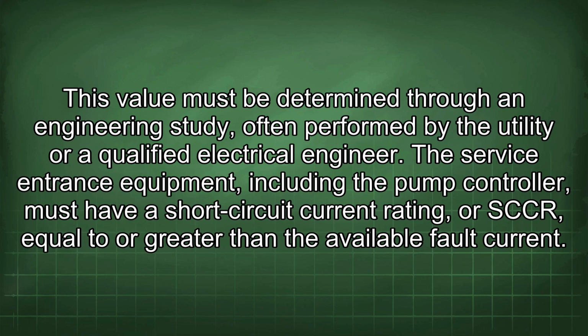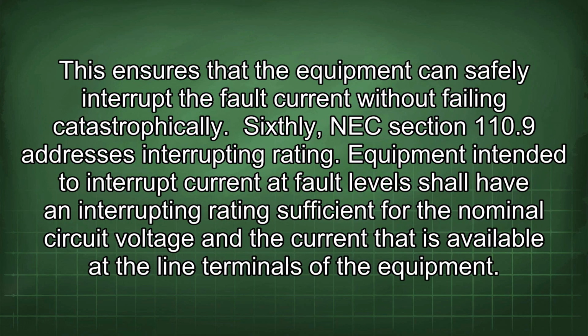This value must be determined through an engineering study, often performed by the utility or a qualified electrical engineer. The service entrance equipment, including the pump controller, must have a short circuit current rating, or SCCR, equal to or greater than the available fault current. This ensures that the equipment can safely interrupt the fault current without failing catastrophically.